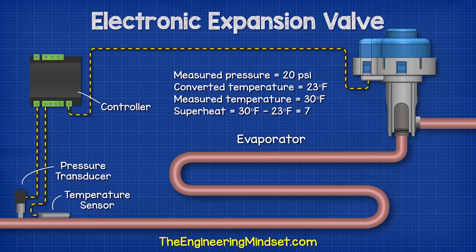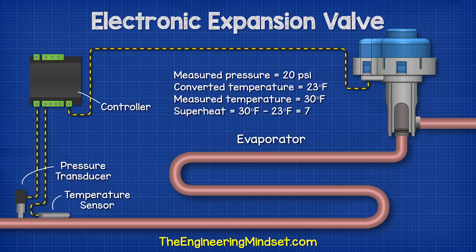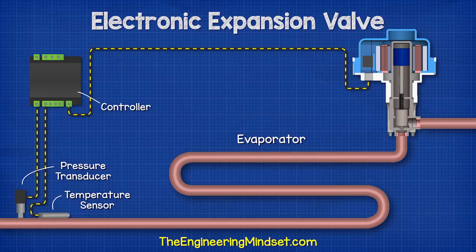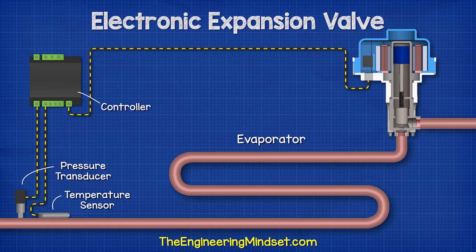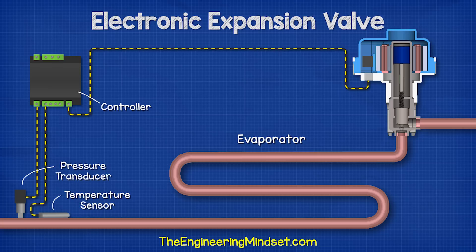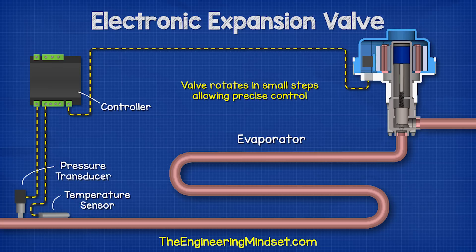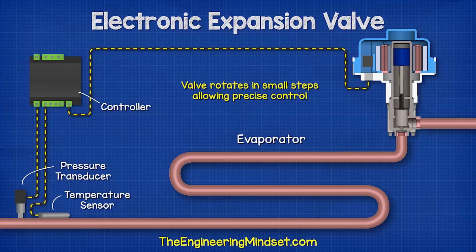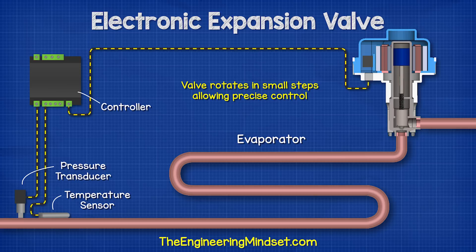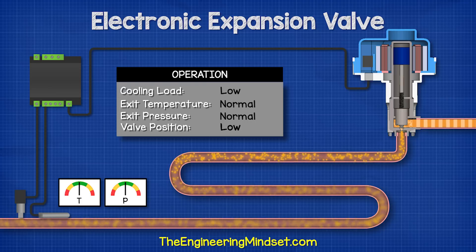The controller sends this signal to the expansion valve stepper motor to energize the coils and create the electromagnetic field. The permanent magnet's magnetic field will interact with this, which causes it to rotate either clockwise or counter-clockwise depending on the signal being sent. The signal causes the valve to rotate a very small amount which allows precise control and adjustment to the superheat.